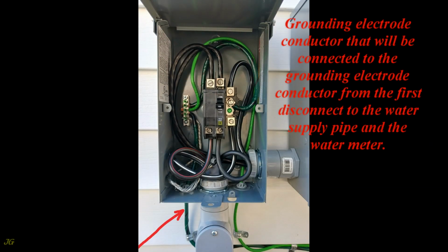Connect the wires from the second service disconnect to the second meter socket in the meter pan in the same way as the wires from the first service disconnect to the first meter socket in the meter pan. Grounding electrode conductor that will be connected to the grounding electrode conductor from the first disconnect to the water supply pipe and the water meter.